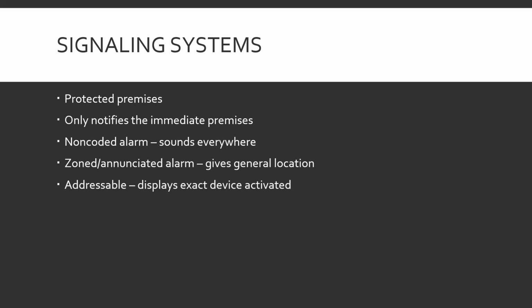And then addressable. These are the most direct systems, in which it tells you what device was activated. For example, in our gymnasium analogy, the fire alarm gets pulled, the fire department shows up and looks at the panel, and it'll say pull station 13827 was activated. Then they can grab the book and go, gymnasium, east wall. Okay, and they go, yep, it's pulled. Problem solved. It tells you exactly what's going on.